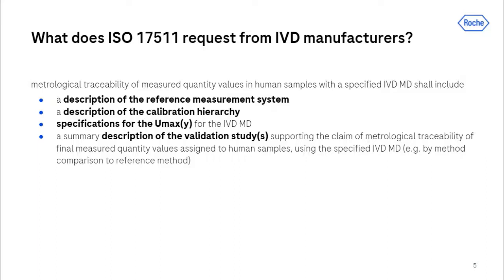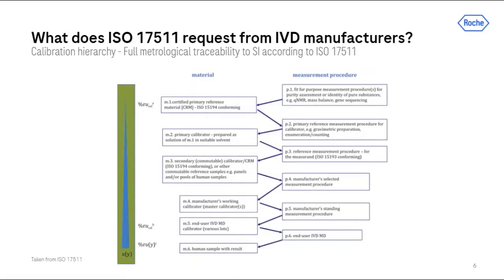Per ISO 17511, IVD manufacturers shall describe the reference measurement system and calibration hierarchy, specify the uncertainty of their device, and also describe the validation studies to show and confirm the claim of metrological traceability. The calibration hierarchy as outlined in ISO 17511 starts preferably with gravimetry or qNMR as the purest and highest-order measurement procedure. The unbroken traceability chain then alternates between value assignment of a lower-order reference material and calibration of a lower-order method, down to the final lowest order — the patient result. With each step downward, the uncertainty increases.